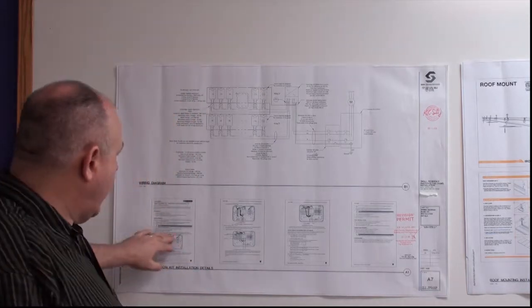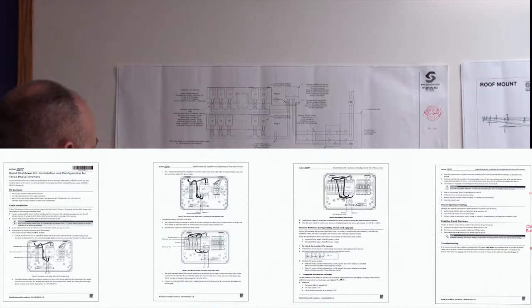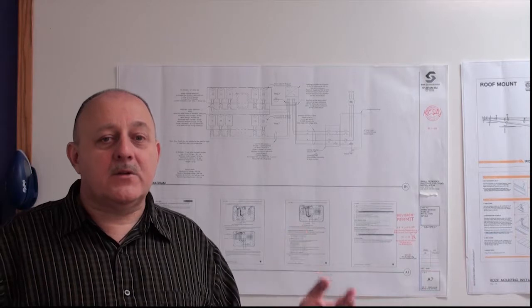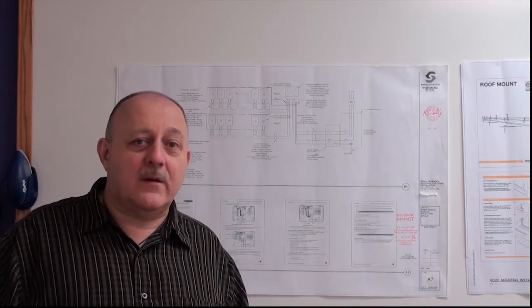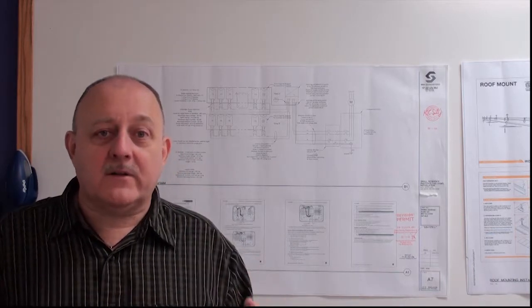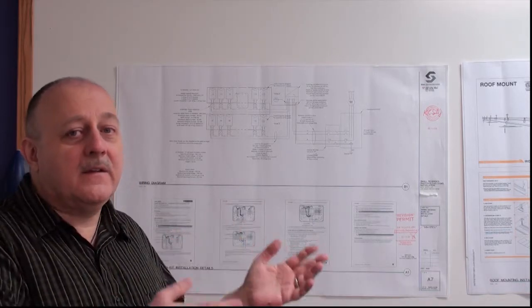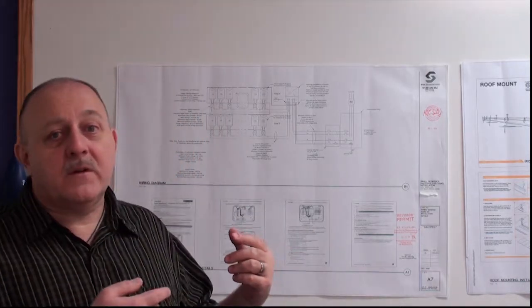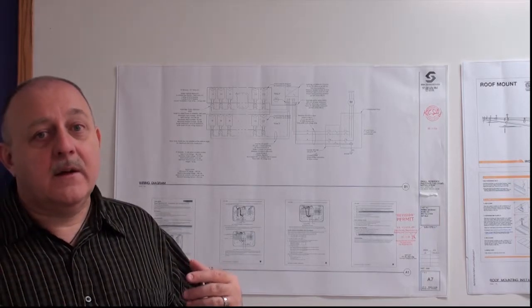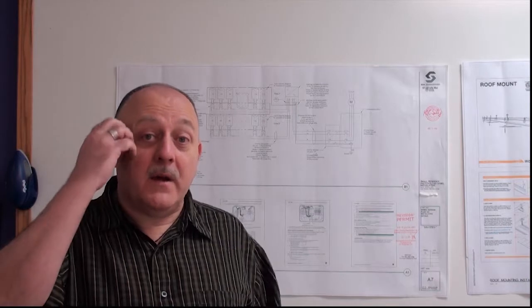So then these diagrams down here are for the rapid shutdown kit. And what the rapid shutdown kit is, something that I think is really, really crazy, but it's a mandate of most building codes. And what it does is it causes the system to shut down when there's no power from the grid. I have to say that over again so that you'll understand it. When you will most want electricity, when the grid is down, the system is designed to shut itself down. And they look at this as a safety issue, that if there was a line worker outside your house and he thought the grid was down and there was no power in it and he was working on the grid, and then your solar system was producing electricity and you didn't cut it off, then you would be able to electrocute him inadvertently by pumping power into the grid.